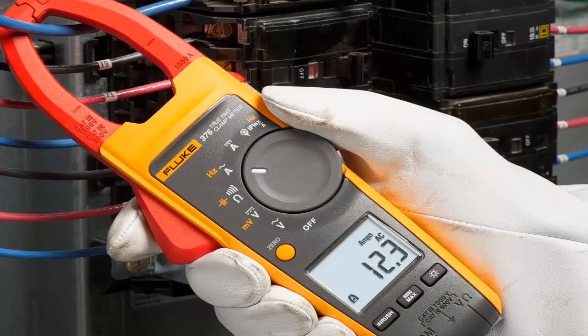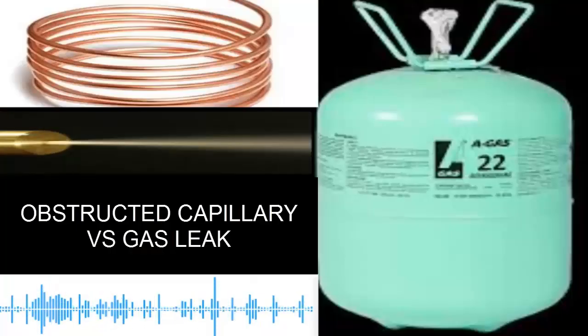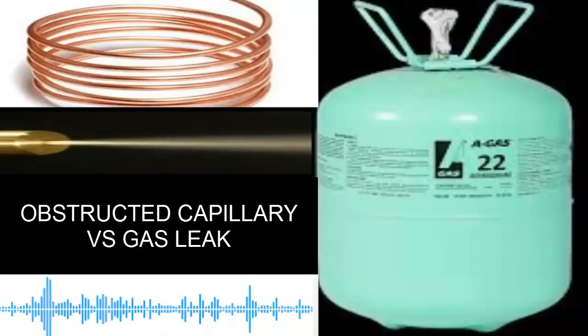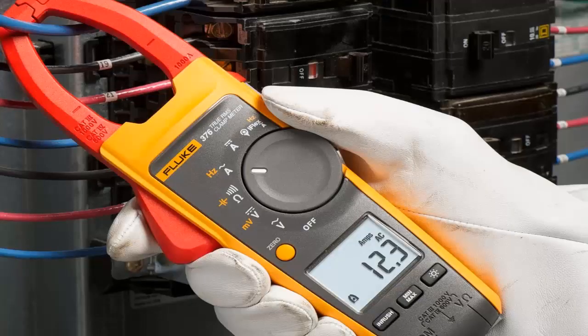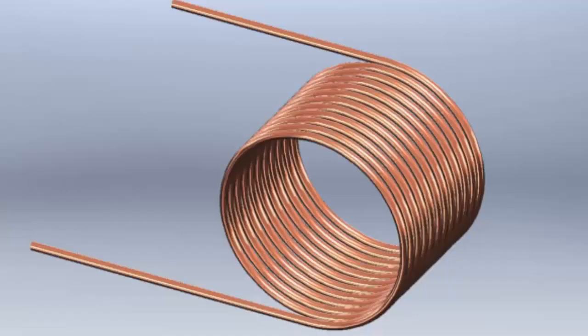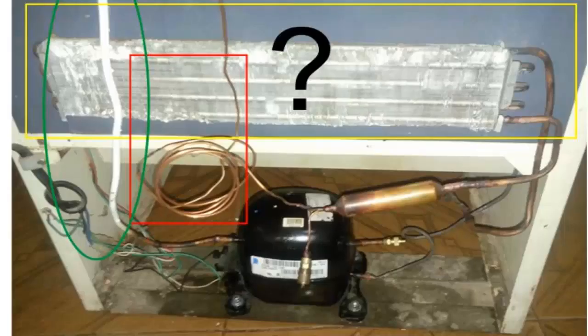B. The lack of gas in the compressor's suction makes the equipment consume less amperage. In this case, you may notice that the evaporator's refrigerant pressure will start to decrease, and the amperage will be below normal. C. Remember that a dry and warm capillary is a good indication that it is not obstructed. But if the capillary is wet or cold, especially towards the end of the capillary length, it is a sign of obstruction.